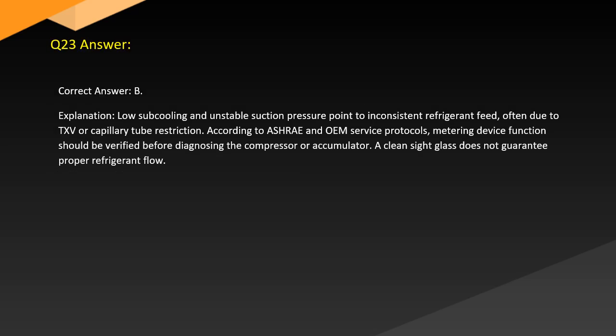Answer. Correct answer. B. Explanation. Low subcooling and unstable suction pressure point to inconsistent refrigerant feed, often due to TXV or capillary tube restriction. According to ASHRAE and OEM service protocols, metering device function should be verified before diagnosing the compressor or accumulator. A clear sight glass does not guarantee proper refrigerant flow.